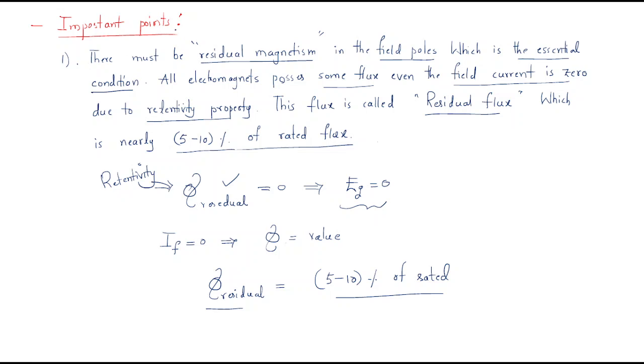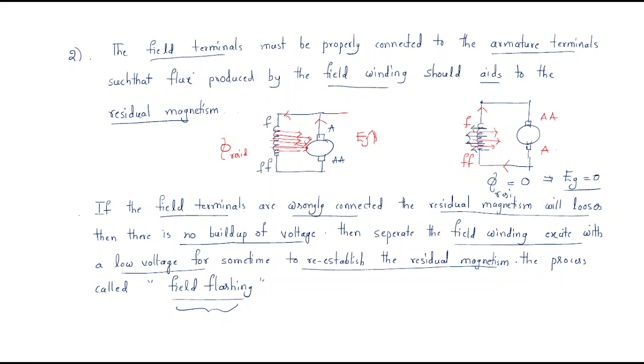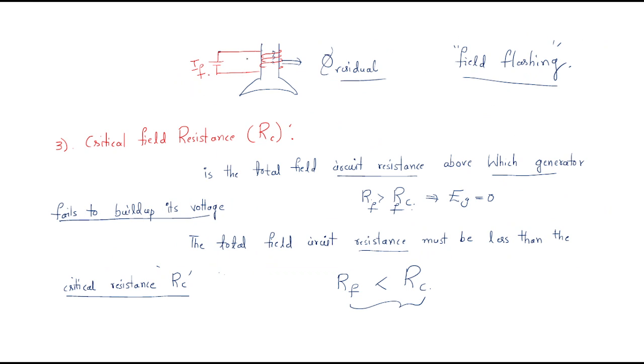In this session, we discuss important points regarding the self-excited generator. We already covered the first point — residual magnetism — and the second point — field flashing. Whenever the residual magnetism becomes zero, we give a small DC excitation to the winding, then the residual magnetism will be recovered. That is called field flashing.